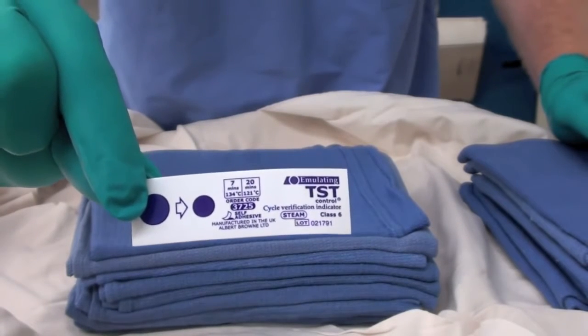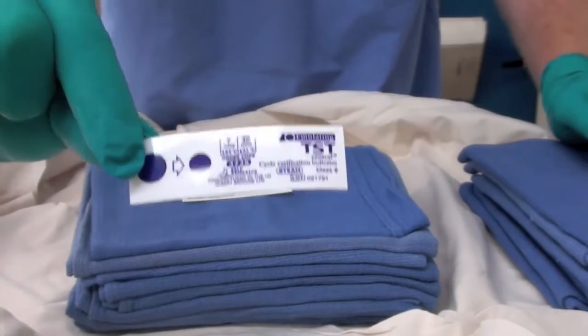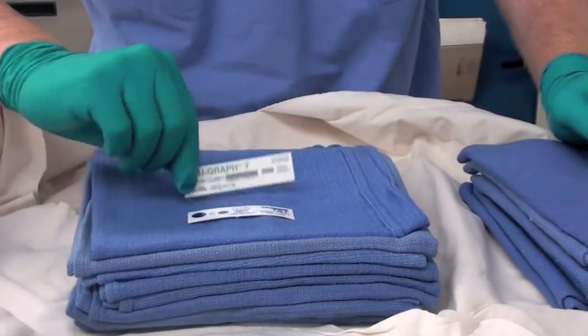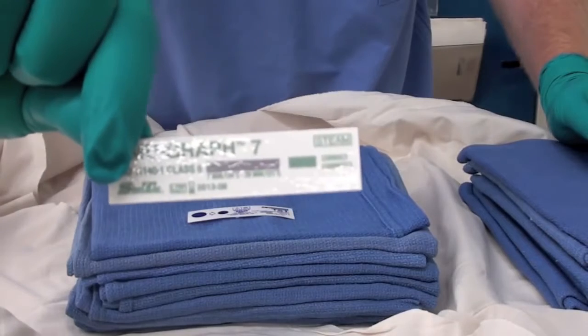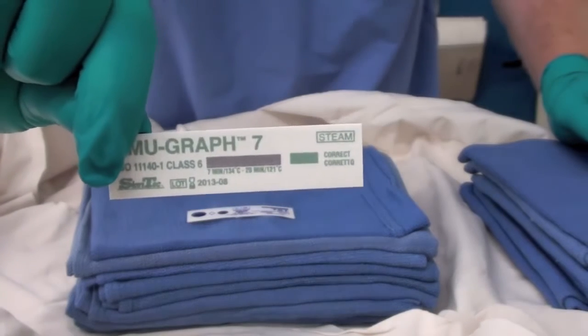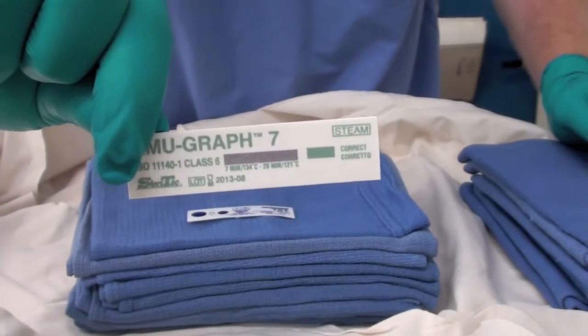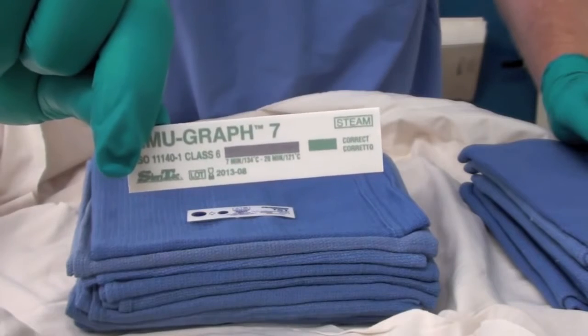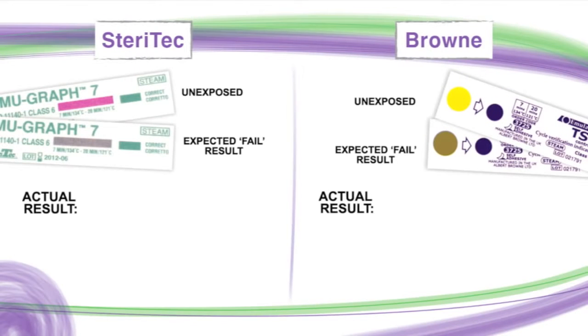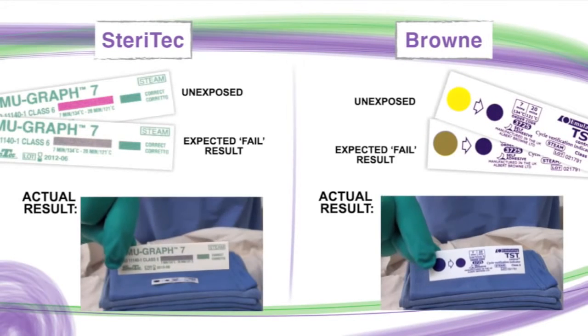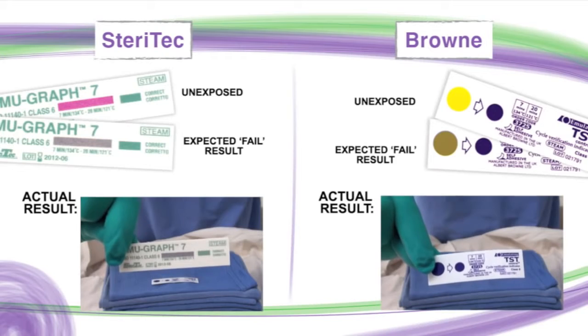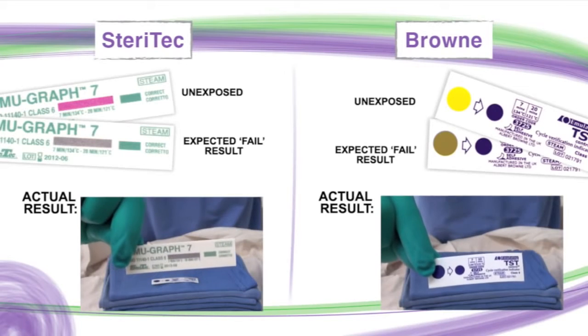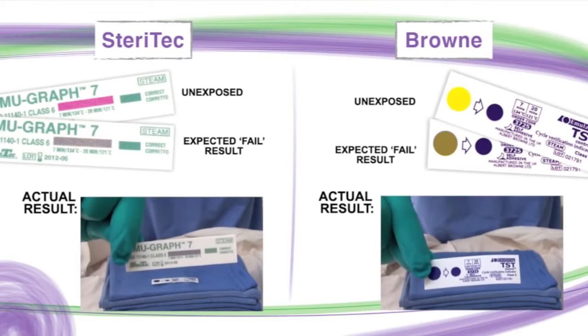In the same cycle and towel pack, the SteriTec indicator demonstrated a clear fail result with purple color remaining as expected. This is a clear sign that complete sterilization conditions have not occurred. Sterile processing professionals would immediately know that this cycle was insufficient and could take corrective action. In summary, the Browne product shows a pass when it should have failed, while the SteriTec product shows a fail, as expected. The SteriTec product is clearly better at detecting failed cycles, which enhances patient safety.